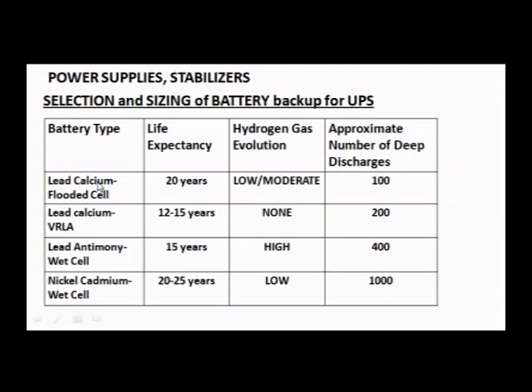For lead calcium, it's 20 years life expectancy, hydrogen gas evolution low to moderate, with approximately 100 deep discharges. Another lead calcium type gives 12 to 15 years, no hydrogen gas evolution, and 200 deep discharges. Lead antimony, a wet cell, gives 15 years life expectancy, high hydrogen gas evolution, and 400 deep discharges. Nickel cadmium gives 20 to 25 years, low hydrogen gas evolution, and up to 1000 deep discharges. So depending on the battery type and expected life, you can decide which battery backup you want for your UPS system.